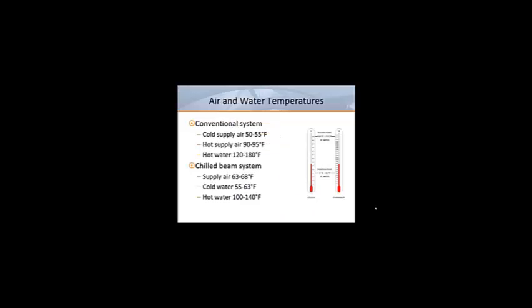Now let's look at temperatures. In a typical office situation, the desired room temperature is 72 to 74 degrees Fahrenheit. In a conventional system with an air handler and overhead diffusers, the supply air for cooling is 50 to 55 degrees, and the supply air for heating is 90 to 95 degrees. If the supply air must be reheated by a terminal unit by means of a hydronic coil, it would typically be supplied with 180 degree water.